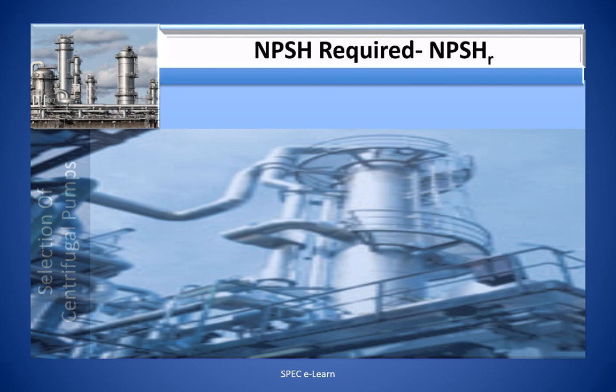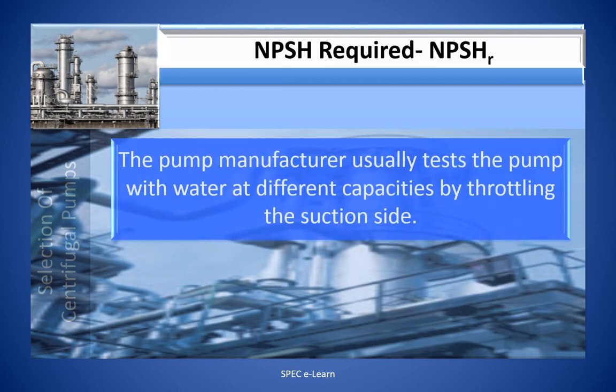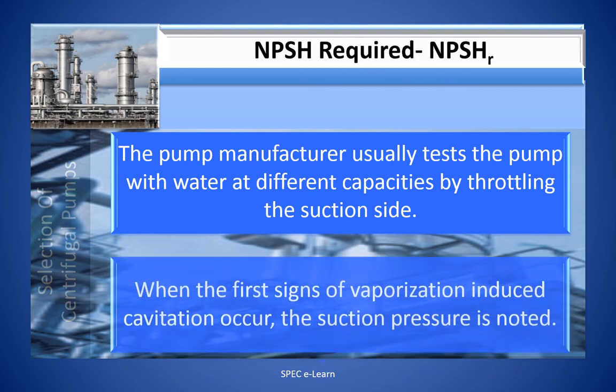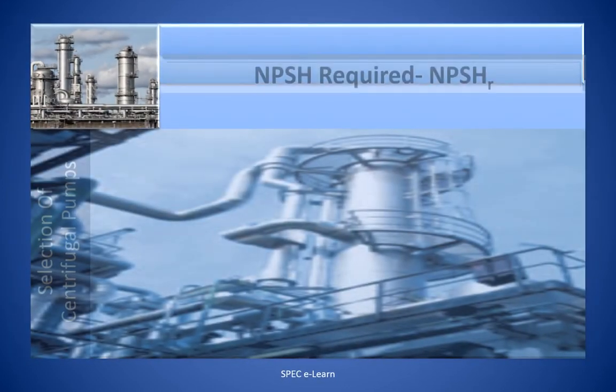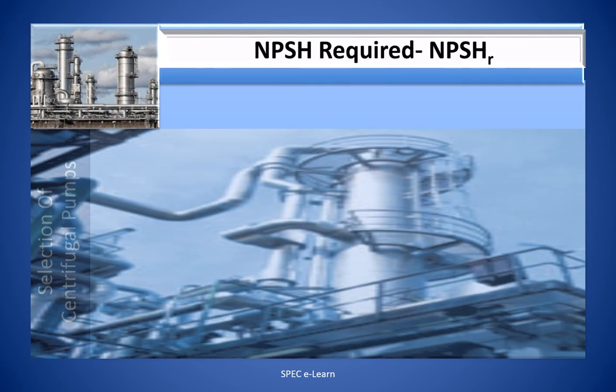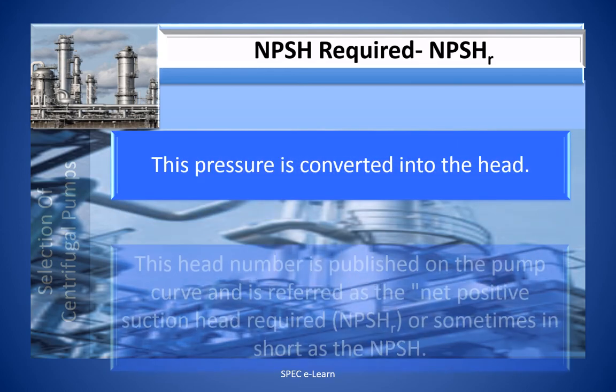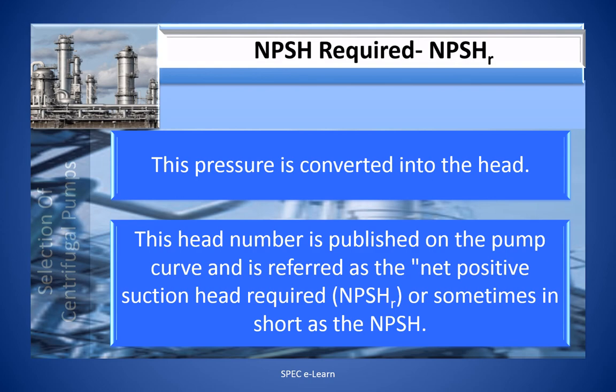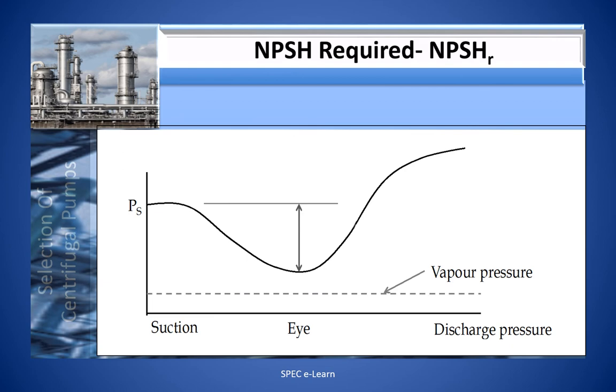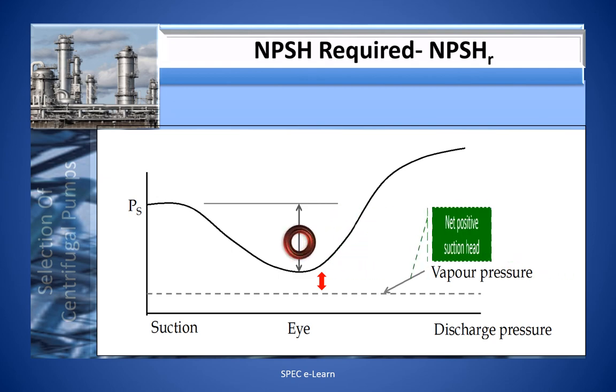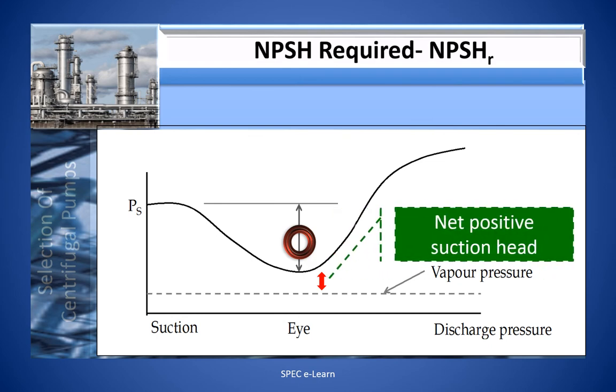The pump manufacturer usually tests the pump with water at different capacities by throttling the suction side. When the first signs of vaporization-inducing cavitation occur, the suction pressure is noted and converted into head. This head number is published on the pump curve and is referred to as the net positive suction head required (NPSHR). NPSHR is a function of pump design and is determined based on actual pump tests by the vendor.